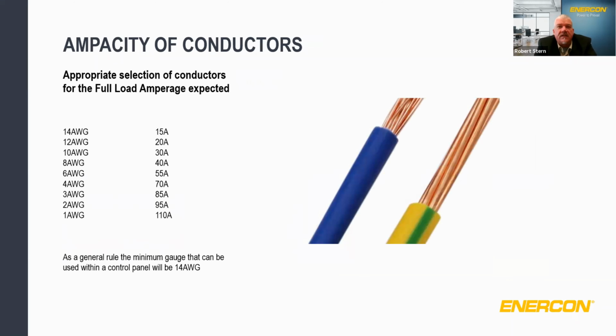Ampacity of conductors. Careful consideration must be made with respect to the wire gauge of the conductors within the industrial control panel. All the internal wiring within the control panel itself should be stranded copper wire with UL approved insulation when used in both class one and class two circuits. As a general rule, the minimum wire gauge used within the panel is about 14 gauge, except for conductors that were originally supplied by the manufacturer to devices within a class two circuit or a low voltage limited energy circuit. So this would be like a secondary transformer, some type of PLC or sensor device that's used in a low voltage circuit.